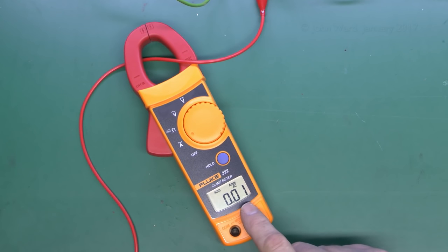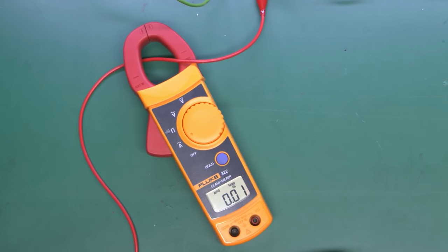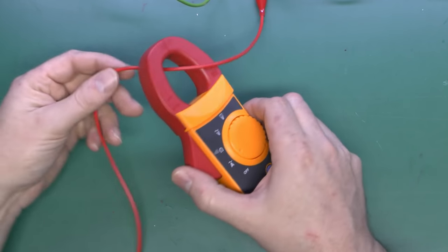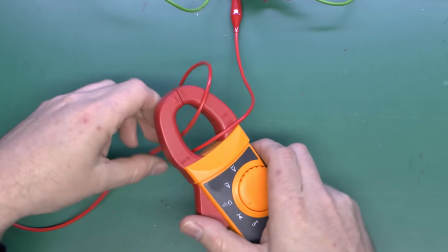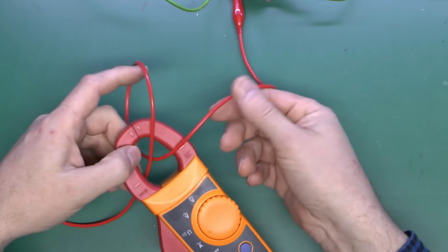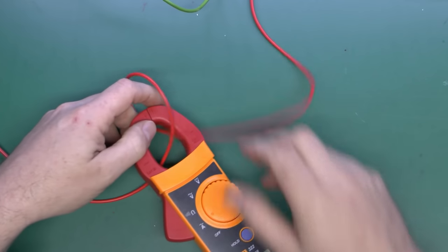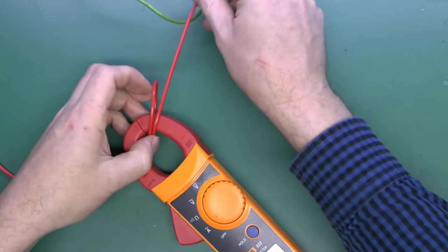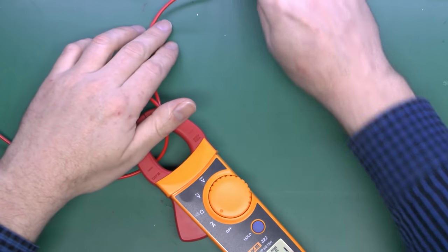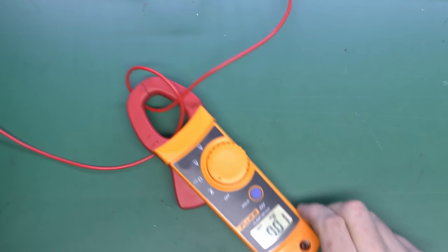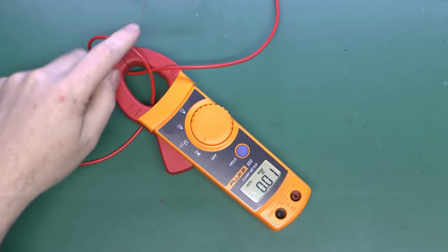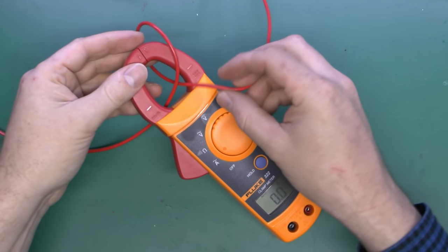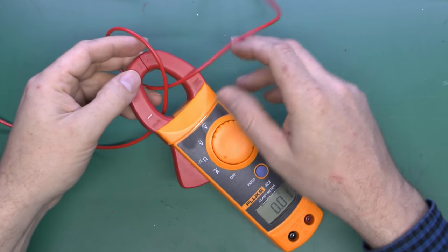Now if you're going to measure a very low current, say lower than the thing is really intended for, what you can do is instead of just putting a single loop through here, you can actually put two loops through. If we loop that around, we've now got two wires effectively going through here, although they both happen to be the same. So what we should now see is the current on the display is double what it was before.